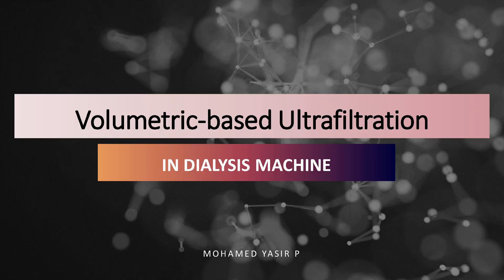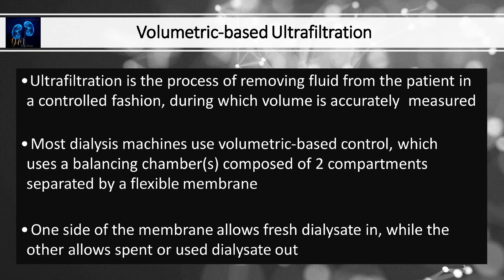Today we are going to discuss volumetric-based ultrafiltration control in hemodialysis machines. Ultrafiltration is the process of removing fluid from the patient in a controlled fashion, during which the volume of ultrafiltration is accurately measured. Most dialysis machines use volumetric-based ultrafiltration control, which uses a balancing chamber composed of two compartments separated by a flexible membrane.